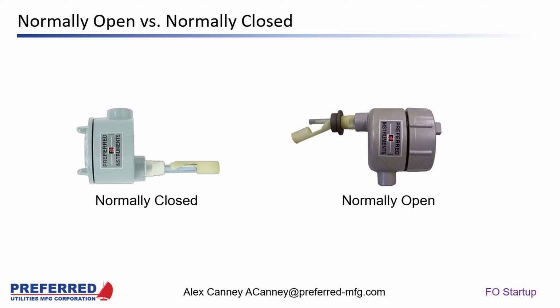I look at that as an advantage, because that tells me not only the state of the switch, but also that the wiring is correct. So if I have a normally open field switch, that makes me think I should probably check the wiring as well, maybe ring it out on both ends to make sure that's correct. But with normally closed, I know that the circuit is completed, right? So that tells me not only that if it's a leak switch, I'm not in leak alarm and my wiring is whole, but further than that, I've noticed that there can be a lot of confusion about the term normal. And we see that especially on day tank level switches.